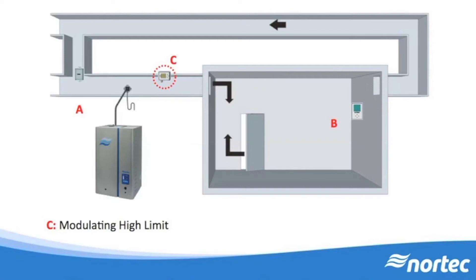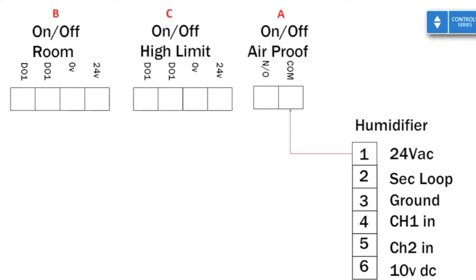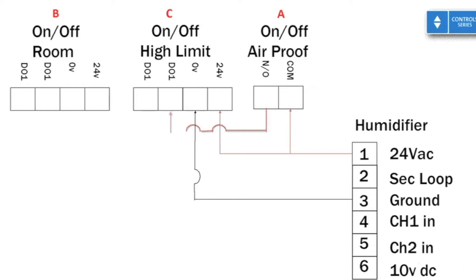The on-off high limit humidistat requires power and ground from the humidifier. We use 24 volts AC from the humidifier, pin 1, wired to the respective terminal on the humidistat, and ground, pin 3, to the respective ground pin. The conductor from the air proving switch is used as the incoming signal to the humidistat relay. Since we've placed a high set point, the humidistat calls for humidity unless we reach too high a reading. The relay output then goes to the final device in the on-off chain: the room on-off humidistat.